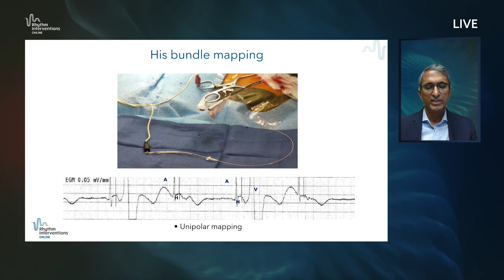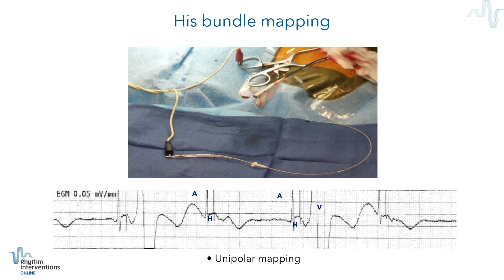So here we predominantly use unipolar mapping during His bundle pacing. The lead tip is just outside the sheath, and you can make this unipolar connection and have all this unipolar electrogram to demonstrate that you can achieve excellent electrogram recording from just a pacing lead. Another important thing is to be able to simultaneously display both using the PSA and the EP recording system. So we have these connections.